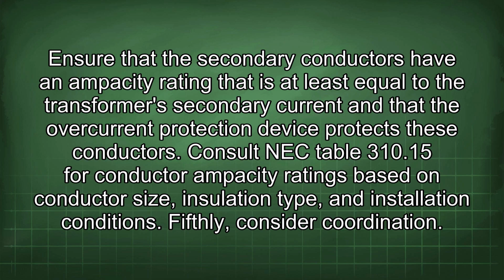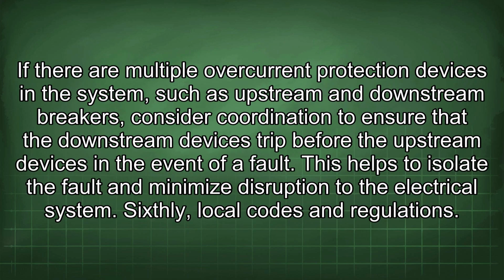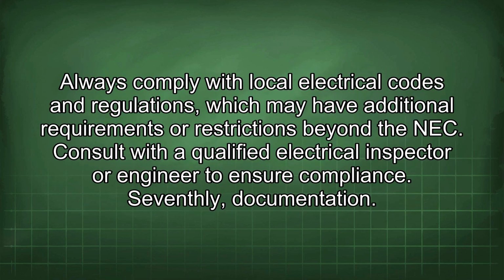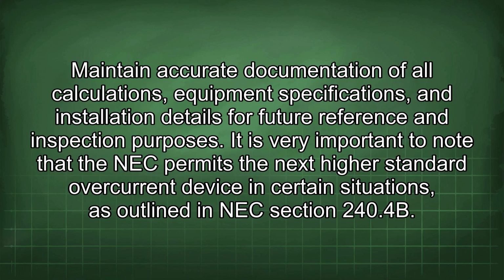Fifthly, consider coordination. If there are multiple overcurrent protection devices in the system, such as upstream and downstream breakers, consider coordination to ensure that the downstream devices trip before the upstream devices in the event of a fault. This helps to isolate the fault and minimize disruption to the electrical system. Sixthly, local codes and regulations. Always comply with local electrical codes and regulations which may have additional requirements or restrictions beyond the NEC. Consult with a qualified electrical inspector or engineer to ensure compliance. Seventhly, documentation. Maintain accurate documentation of all calculations, equipment specifications, and installation details for future reference and inspection purposes.